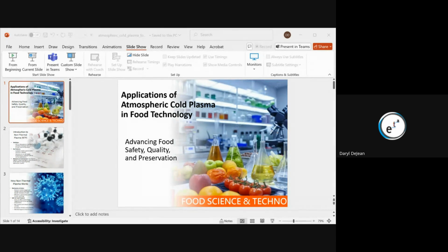But the key feature is it has reactive species, primarily hydrogen peroxide gas and reactive oxygen species. And these species only have a half-life of maybe a millisecond, microsecond, or nanosecond. It doesn't take long to break the DNA and RNA of a pathogen. We'll cover that a little bit more, but that's why it is such a critical thing to remember, that it's producing very controlled amounts of these highly reactive oxygen species with hydrogen peroxide gas.